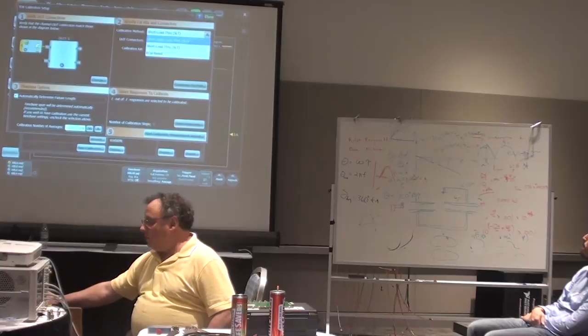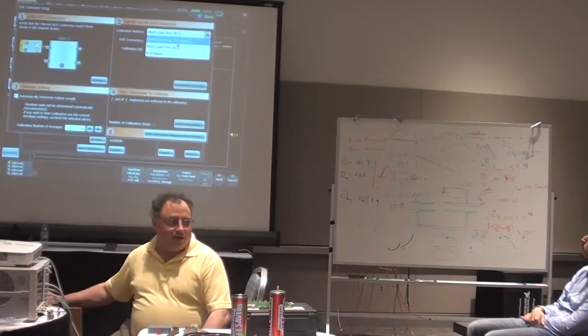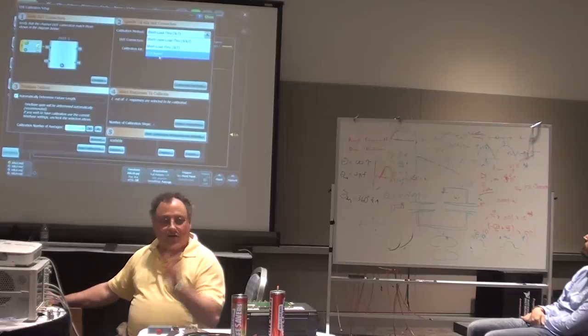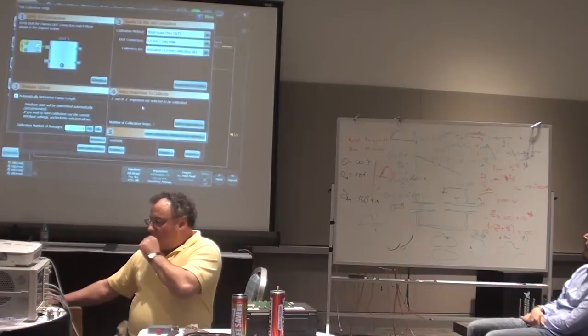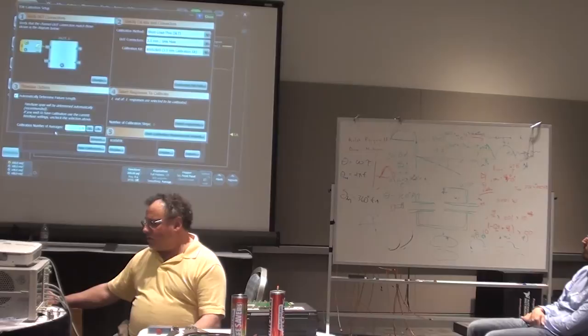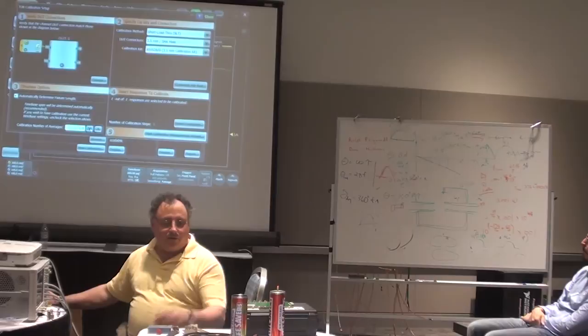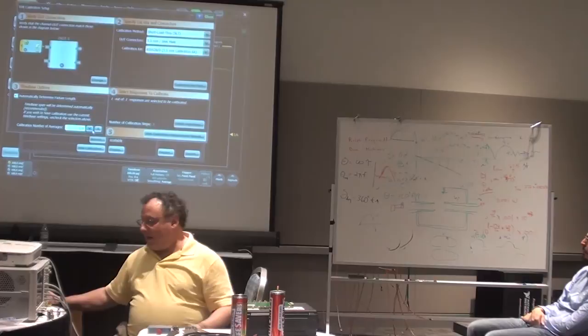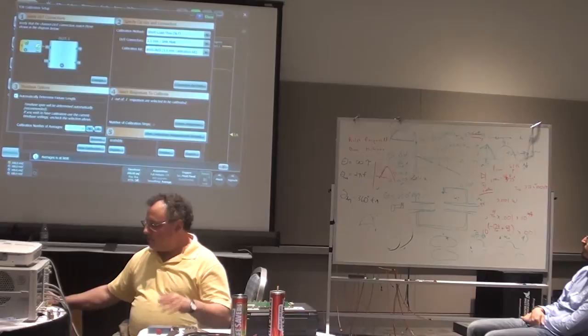Well, we're not going to do any transmission situations, and open circuits are a little hokey. So we're going to just take the short load through technique. ECAL can come later when everyone has figured out, become experts at this. Because it's sampling lots of pulses, things can be kind of noisy. In which case, this thing automatically averages some things. 128 is kind of long, and we're going to have you doing some things like running your fingers along transmission lines, and you don't want the averaging to be sitting there lagging behind. So for this, I think we'll just set this down, and 16 is the limit. So it will always average 16, but it triggers pretty darn quick.